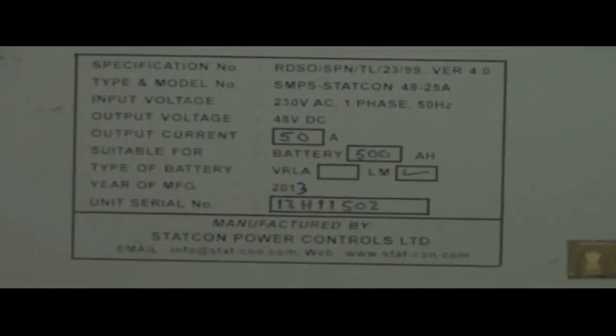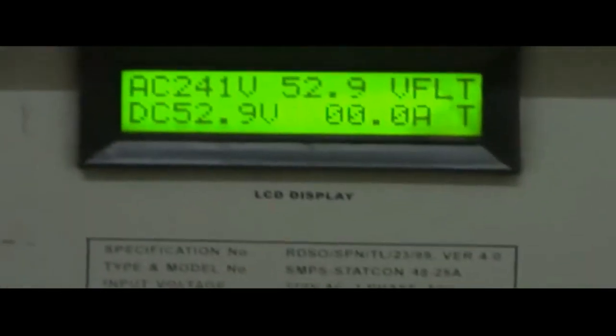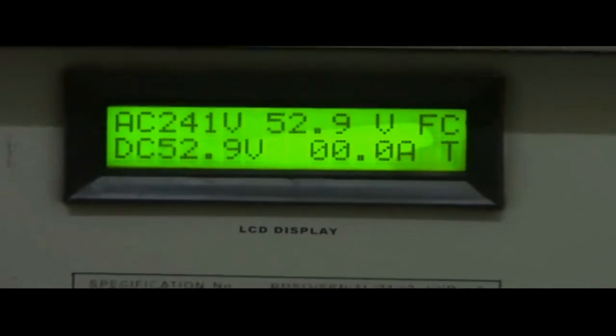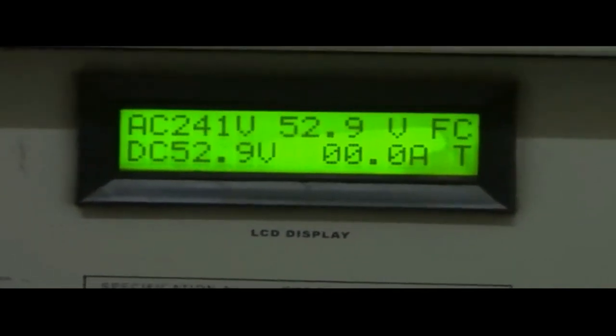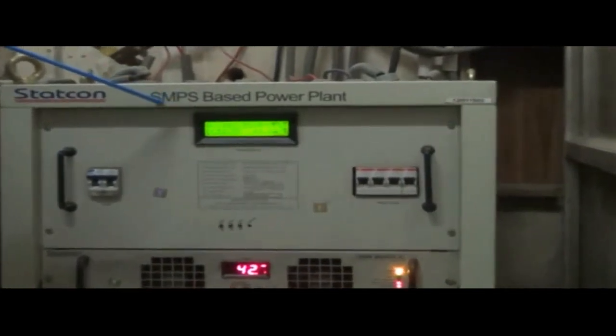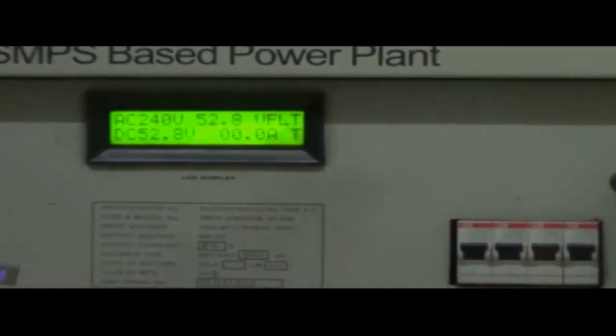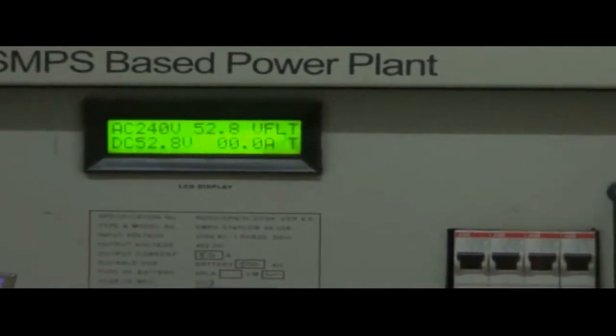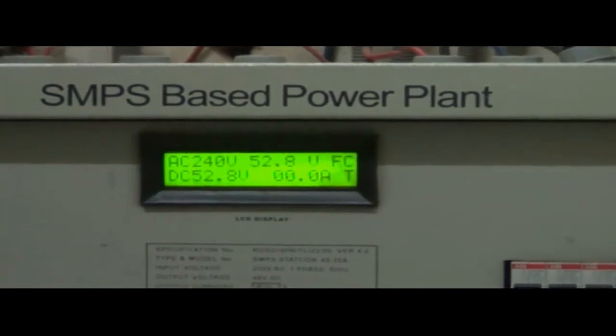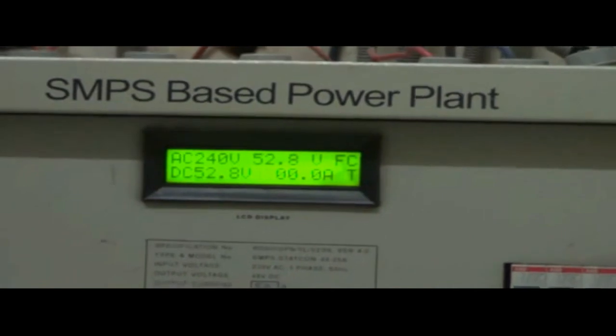This power plant will work either with valve regulated lead acid or conventional lead acid batteries. The main advantage of the switch mode power supply is greater efficiency because the switching transistor dissipates little power when acting as a switch. These are smaller in size and lighter in weight due to elimination of heavy line frequency transformers and lower heat generation.